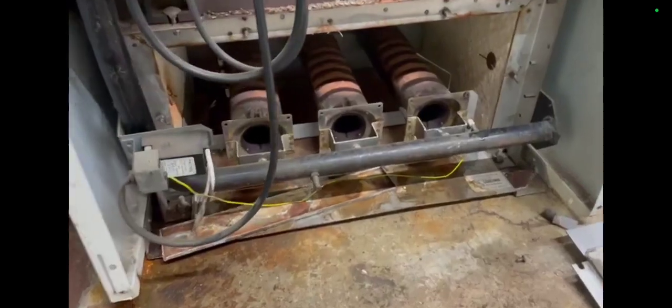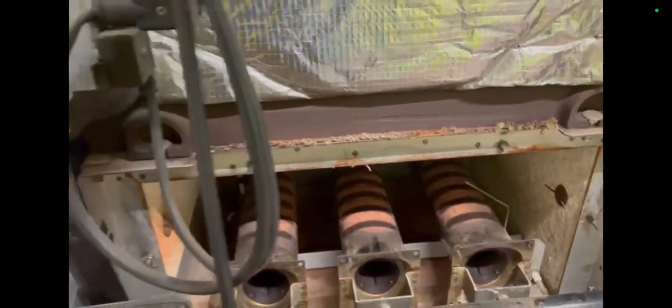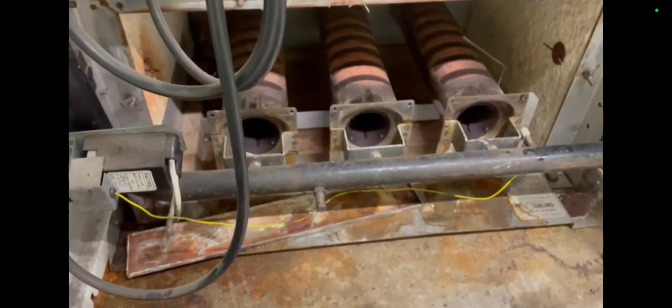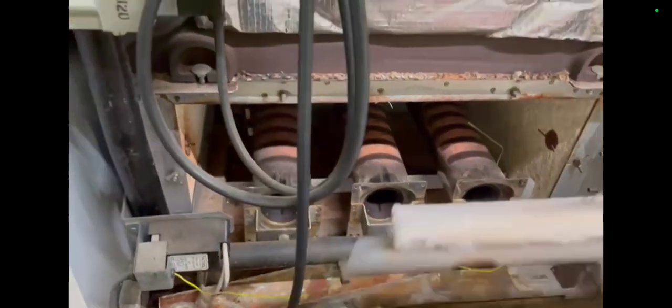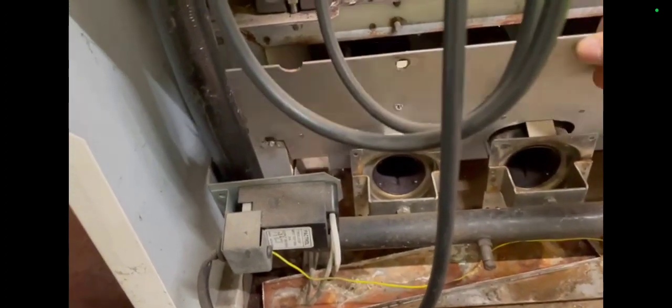Let me show you what happened. So on this side you've got a unit that's not working. I'm looking in at it, it's an Ideal, just to see if there's anything obvious. Seems to keep locking out. Seems to be going out on ignition. These boilers are pretty old, there's still a few around.